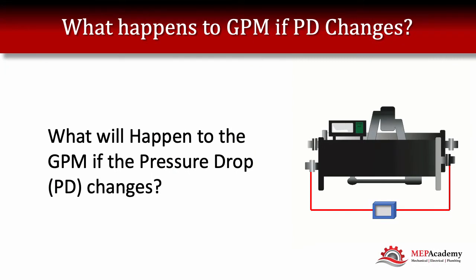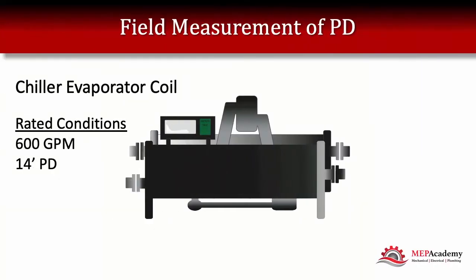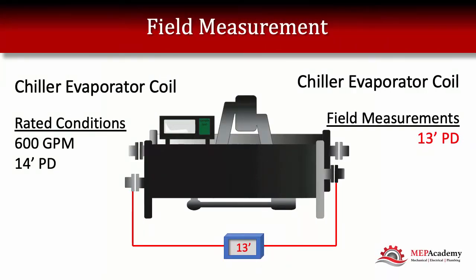So, what will happen to the GPM if the pressure drop increases or decreases? For our example, we're going to take a new chiller that was rated for 600 GPM at 14 feet of pressure drop through its evaporator. When we go into the field and measure the actual pressure drop, we get 13 feet, not 14 as it was rated. So what is this going to do to our GPM?